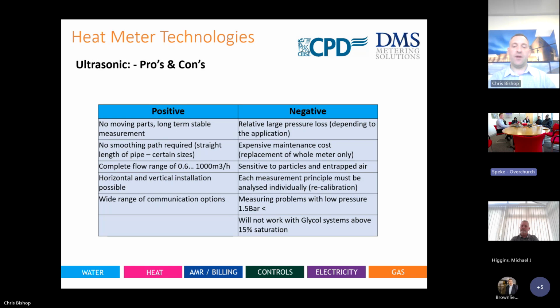So they're designed to measure the flow accurately, but we assist with why you select that meter for that certain branch, or why you can downsize a meter on a certain branch due to the flow rates to save some costs. There's some further conversation to have on that. That's kind of involved in the checklist. They can be mounted horizontal or vertical, which is also why I leave this to this point. The mechanical version can't be installed vertically. The mechanics don't allow it to happen.